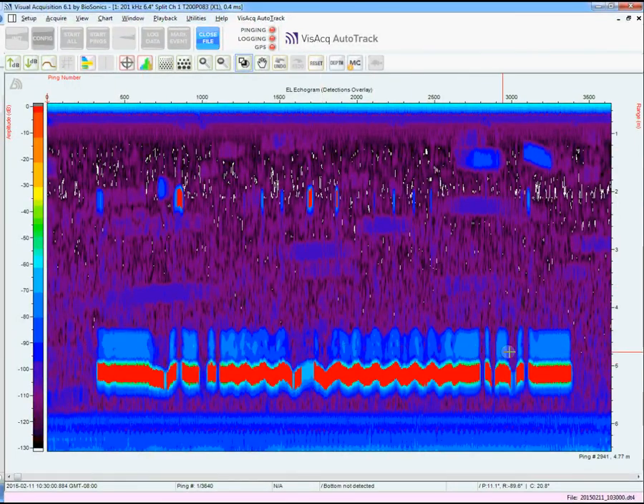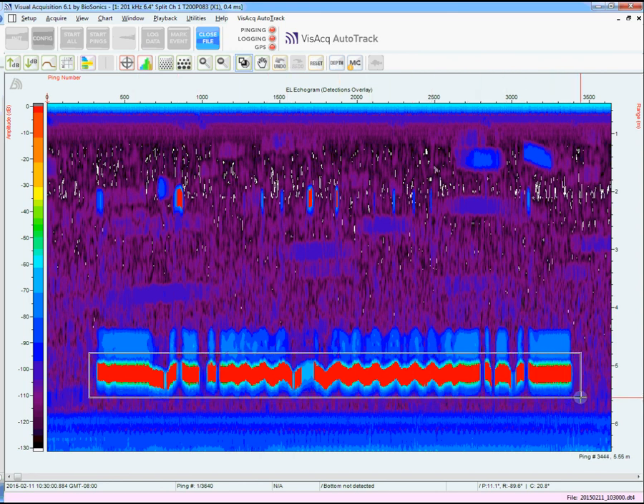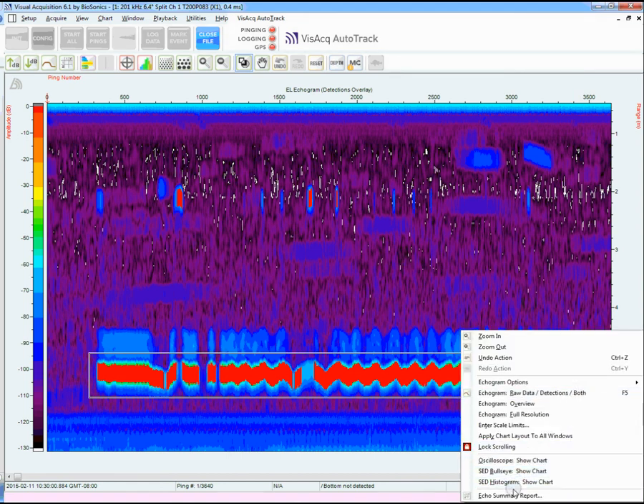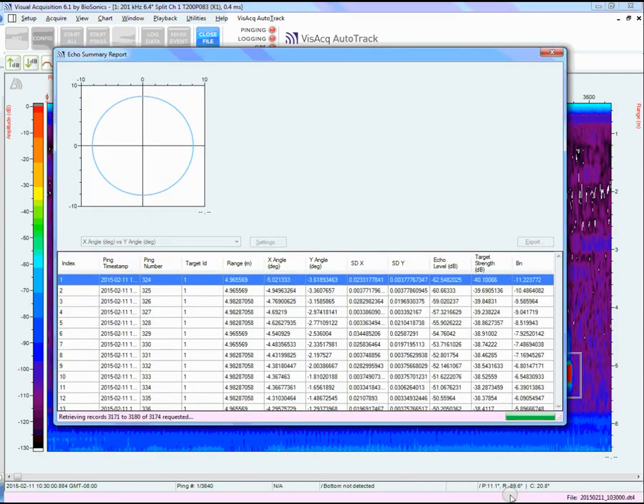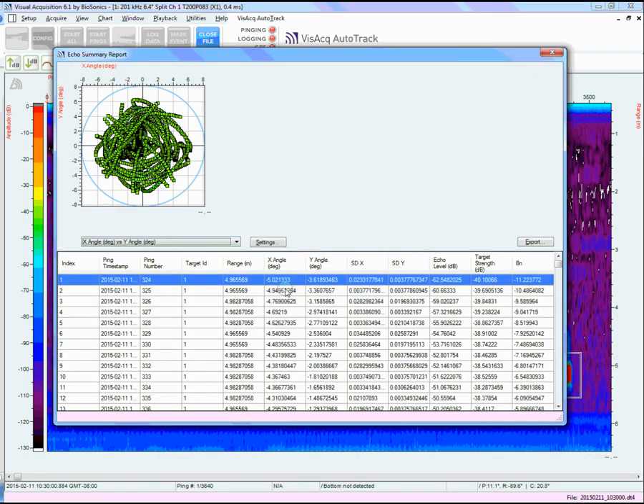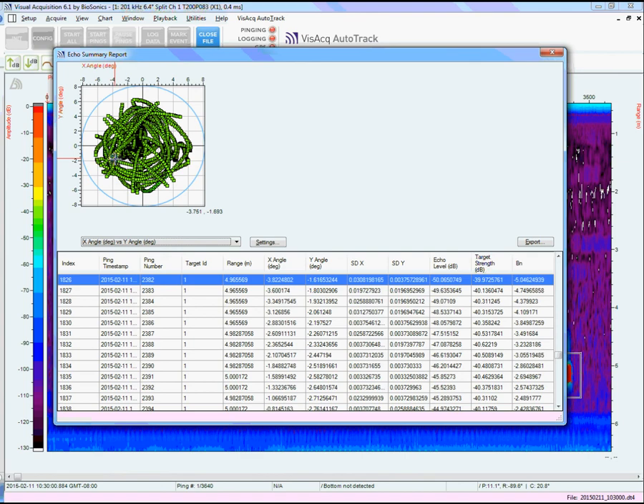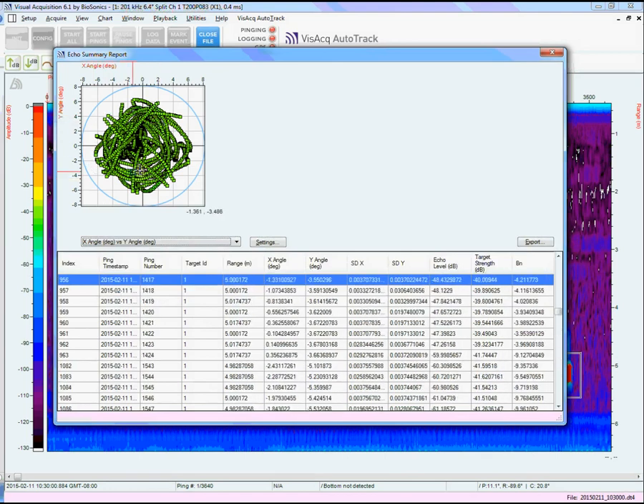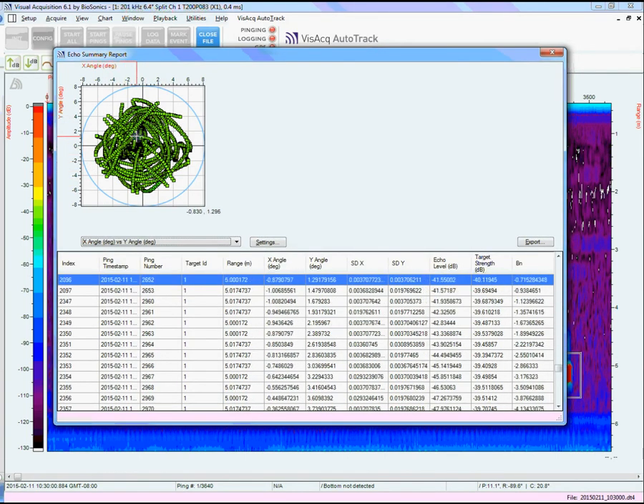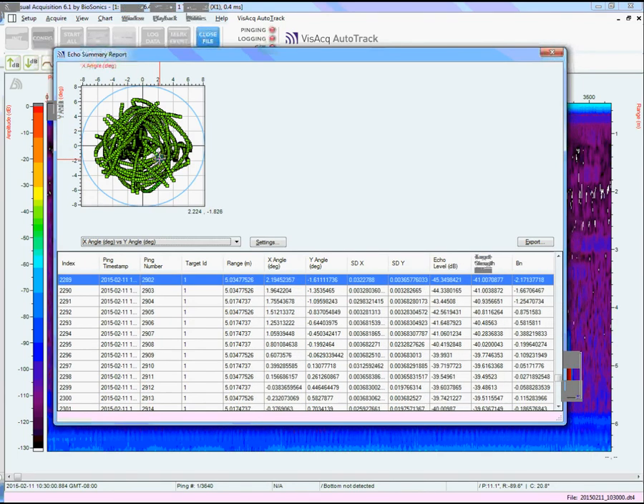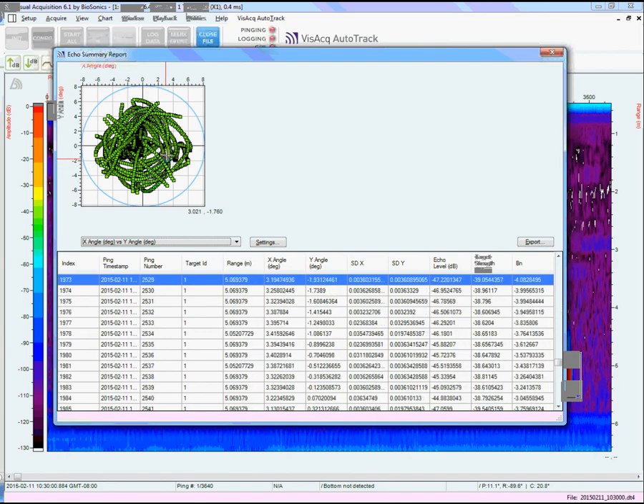So you can see here is our calibration sphere trace. I'm going to draw a box around this. Left click, draw your box around there, and then right click in that box and choose Echo Summary Report. Okay, so this is displaying all of the single echoes that were detected during our calibration sphere data collection. This graph shows the X and the Y angle in the bullseye graph, and as you can see as I scroll over this, the data below is scrolling to show the information for the echo that I have highlighted.